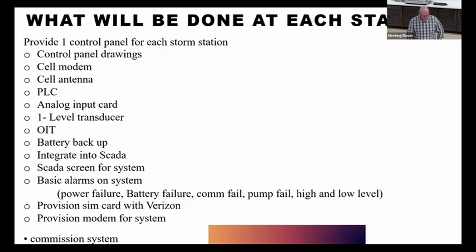Each one of these 3 stations will get 1 control panel, with control panel electrical drawings. It'll have a modem and a cellular antenna to get the signal out, an exterior PLC cabinet, analog input cards, transducers, OIT screens, and a small backup battery unit in case of loss of power.